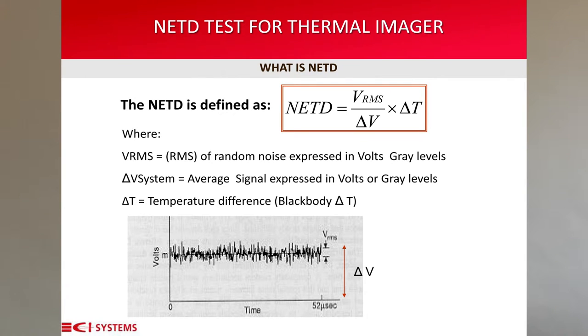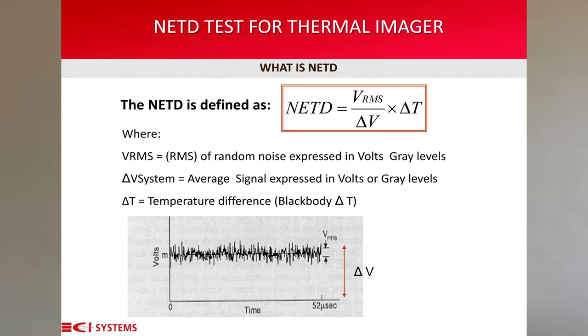The equation defines the method of calculating the NETD of the thermal camera. VRMS equals the measured RMS of the temporal random noise, expressed in volts or gray levels. Delta V system equals the average measured signal, expressed in volts or gray levels. Delta T is the temperature set by the black body, usually set to 2 or 3 degrees. It has to be within the linear segment of the dynamic range of the camera, as measured by the SITF test. It is important to perform the test under controlled conditions.